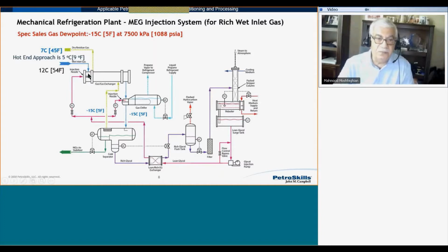So the gas, I put in the tubing of the shell and tube heat exchanger, and I know I'm going to go below the hydrate formation temperature, so I'm going to inject glycol, ethylene glycol, or MEG as Europeans, the rest of the world may call it, and I'm making sure the hydrate inhibitor goes through every tube. And by the time I get out of here, my temperature is cooled down. The process gas temperature cooled down to minus 8.8 degrees Celsius or 15.9 degrees Fahrenheit.